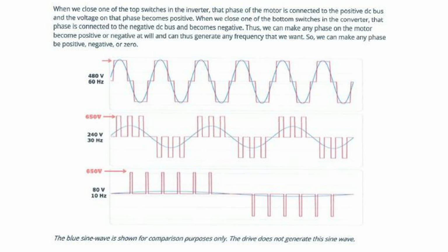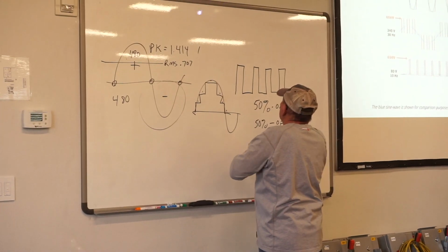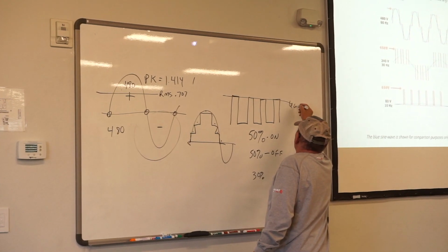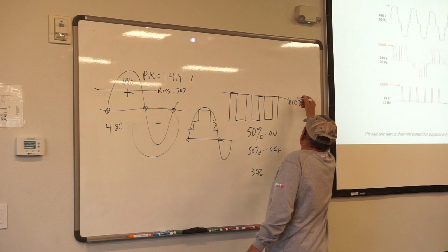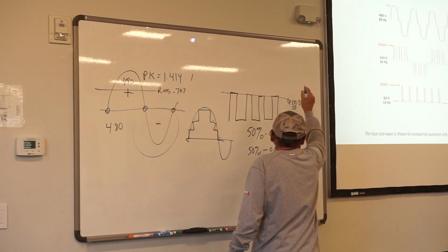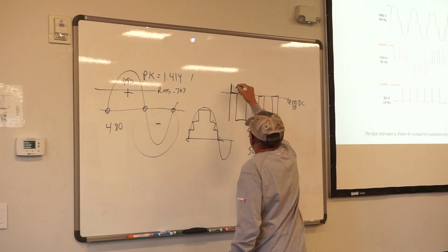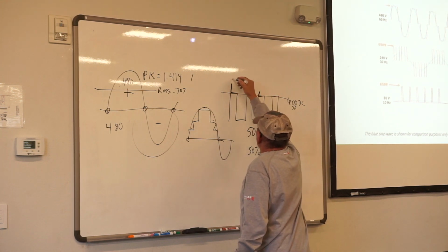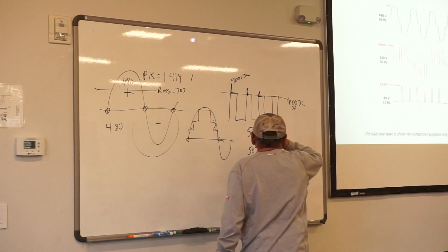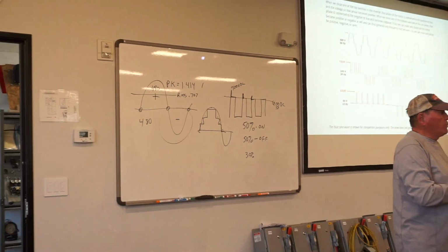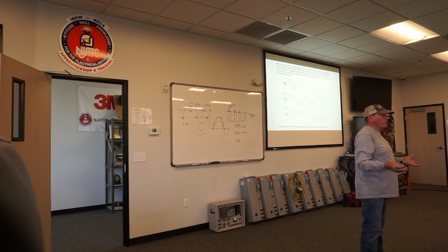So I'm not only controlling the frequency in hertz, at the same time I'm also controlling the voltage to that motor. The problem we have with modulated signals is, remember, this is 600 volts DC, or 650 on the drive. The problem is the leading edge of these pulses is somewhere around 900 volts DC. Why is that? Inrush to the motor, what, 6 to 10 times run load, right?